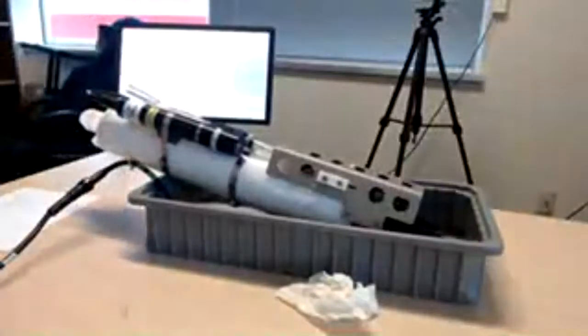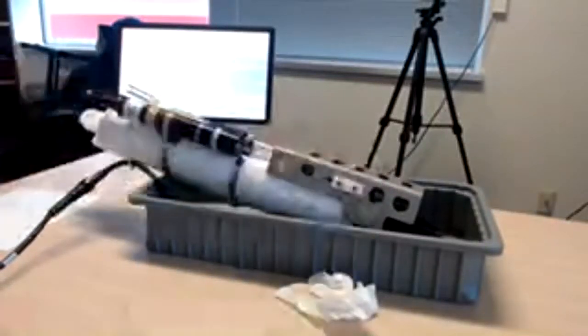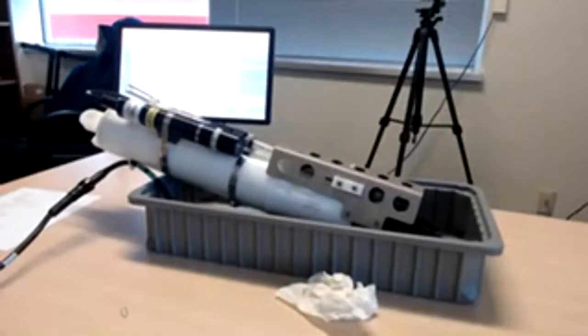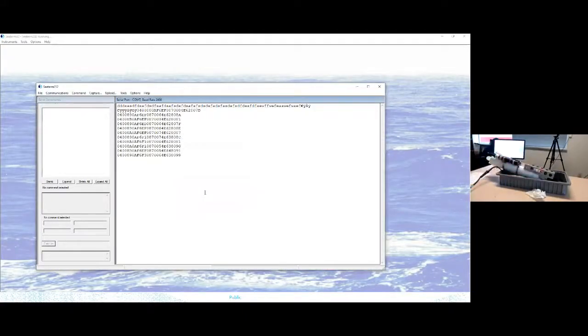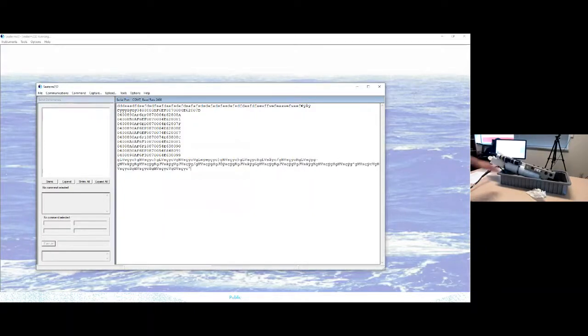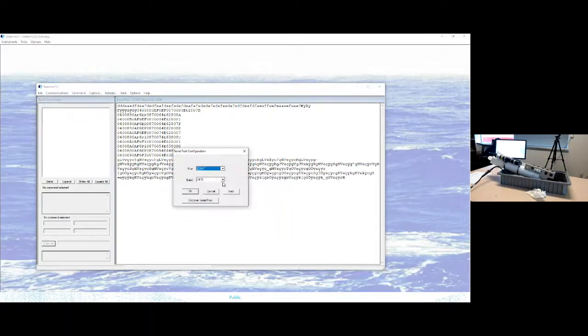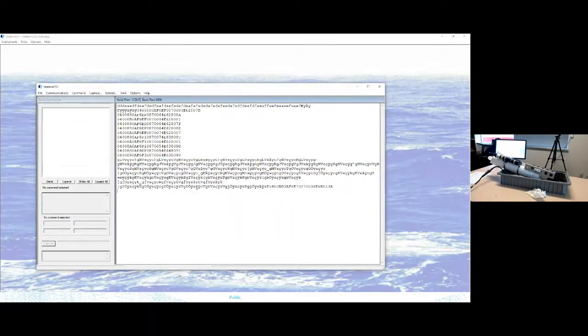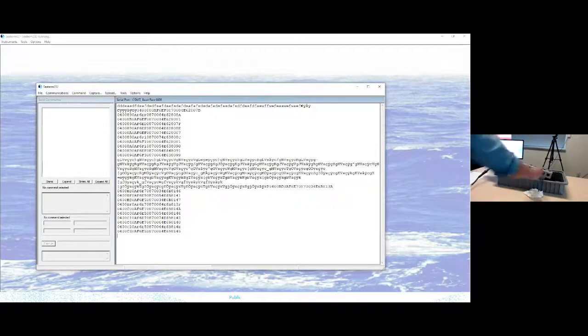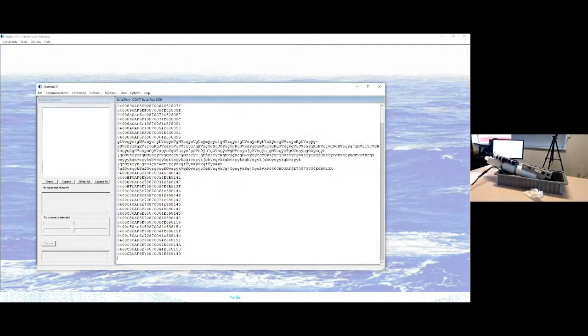If you are connecting at the incorrect baud rates, data you get from your CTD might just be garbled. The characters you see will be unusual. It'll look like garbage. What that means is your CTD is maybe communicating at 9600 baud, but you have CTerm configured to communicate with CTD at, say, 2400 baud. So you could try different baud rates until you get something that looks a little more like standard CTD data. Okay.